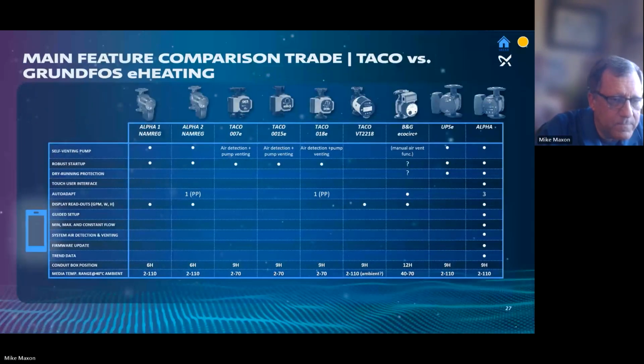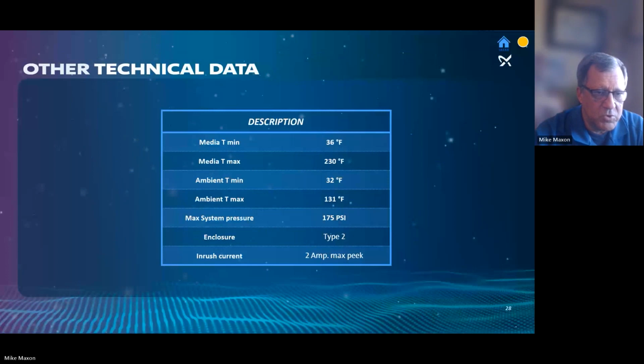Here we have a chart showing all the advantages of the Alpha and UPSe and where they lie with our old Alpha 1, the Alpha 2, as well as our main competitors. I think the Alpha is far and away a better product than anything else that's ever been on the market. 230 degrees, 55 or 131, 55 Celsius or 131 Fahrenheit ambient. That's really quite good for an electronic device. 175 PSI. So we passed that old 145 that we've always been at before.